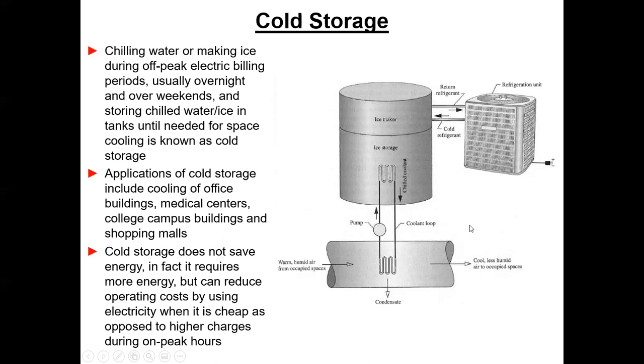Cold storage does not save energy — in fact, it requires more energy — but it can reduce operating costs by using electricity when it is cheap, as opposed to higher charges during on-peak hours. What makes this go is the time-of-day metering and electric rates that some utilities have implemented. During the cheap periods you can run your big water chillers, store cold water or ice, and then leave the big refrigeration machines off during the on-peak period to save significantly on your electric bill.